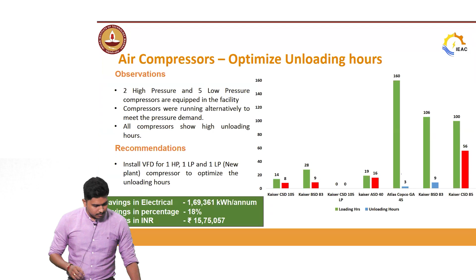This is a classic example where simply changing a pressure setting in your compressor can help — you just go into the settings and change it. This mostly happens in industries due to lack of awareness. When they receive a compressor, the industrial person will install it and automatically configure it to whatever settings he knows, without quantifying the amount of pressure or CFM actually needed.